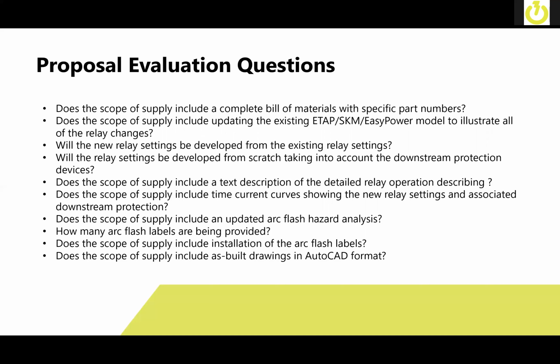So whenever we do these retrofits, again, we're trying to take into account your complete system and take advantage of the new capabilities that the new relays can offer. Does the scope of supply include time current curves showing the new relay settings and associated downstream protection? That way you can visually see and make decisions on the best way to reliably trip your system during a fault. Does the scope of supply include an updated arc flash hazard analysis?